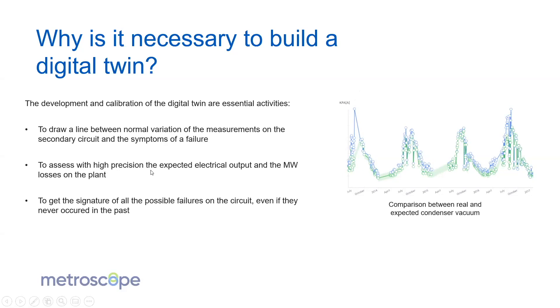It also allows us, since we work a lot with power generation clients, to assess with high precision the expected electrical output — because that's what the client cares about, that's what earns them money. Our clients want to know what megawatts they are losing because of a failure so they can target which maintenance activities are most urgent. And finally, if you want to recognize failures, you need to model them. With statistical modeling, you cannot recognize failures that never happened. But with physical modeling, if we understand a failure, we can model it, get its signature, and recognize it in the future — even if it never happened and the client has no expert on-site.